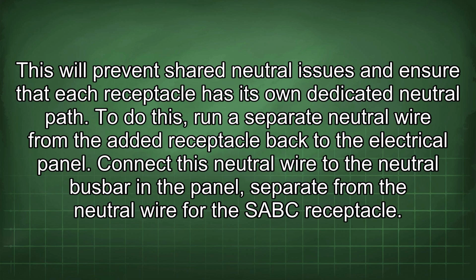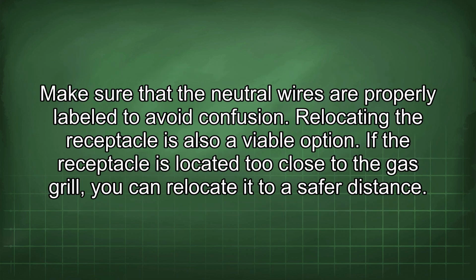To do this, run a separate neutral wire from the added receptacle back to the electrical panel. Connect this neutral wire to the neutral bus bar in the panel, separate from the neutral wire for the SABC receptacle. Make sure that the neutral wires are properly labeled to avoid confusion. Relocating the receptacle is also a viable option. If the receptacle is located too close to the gas grill, you can relocate it to a safer distance.